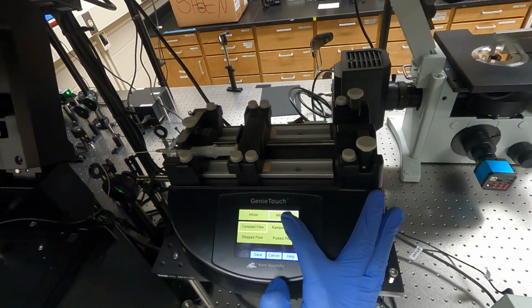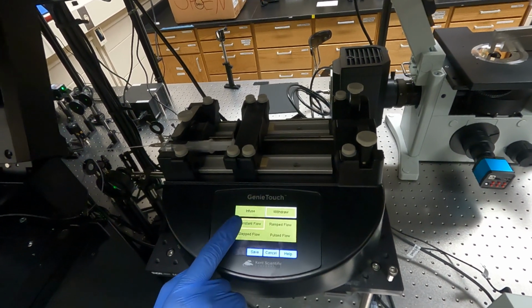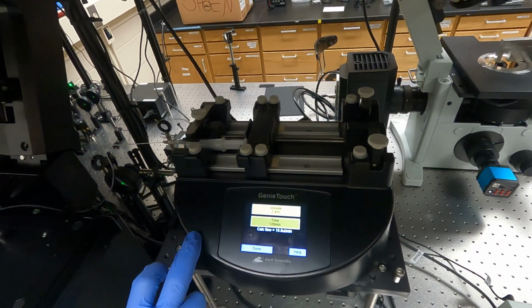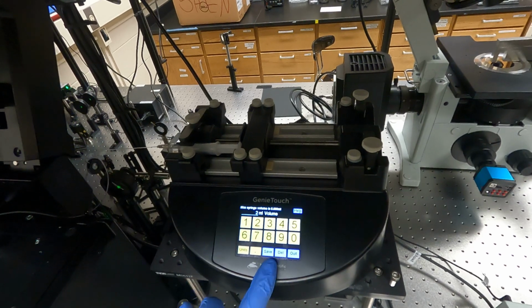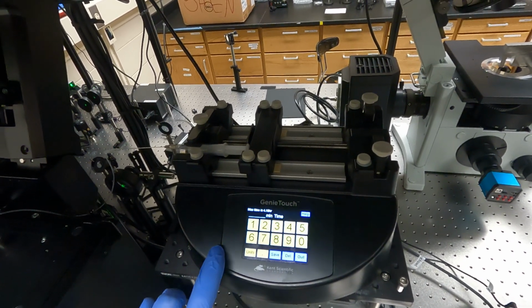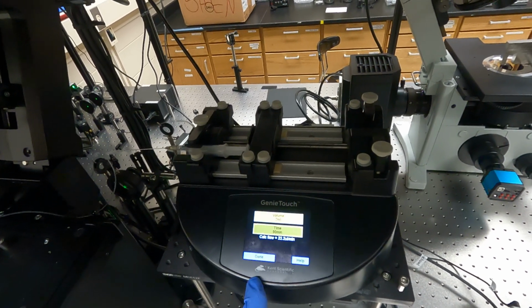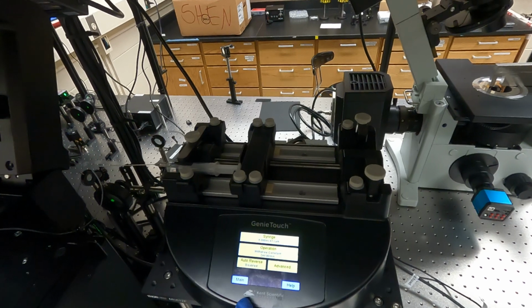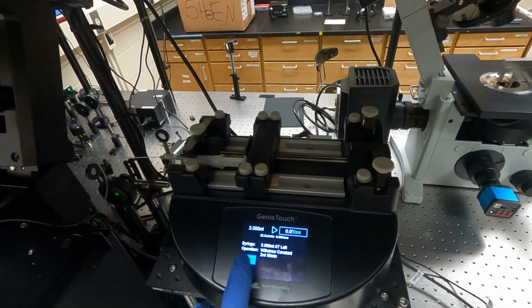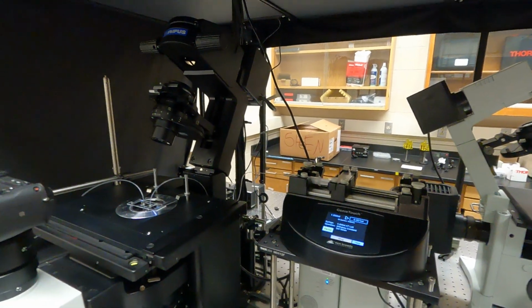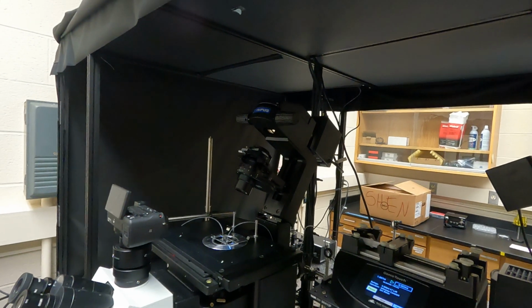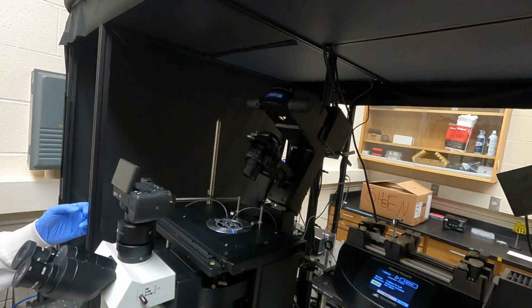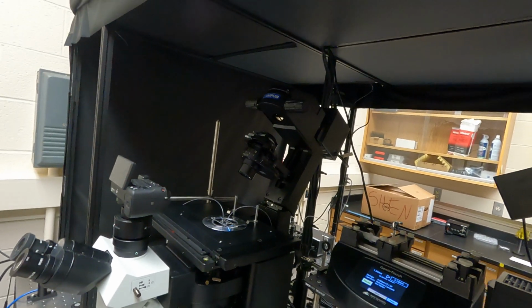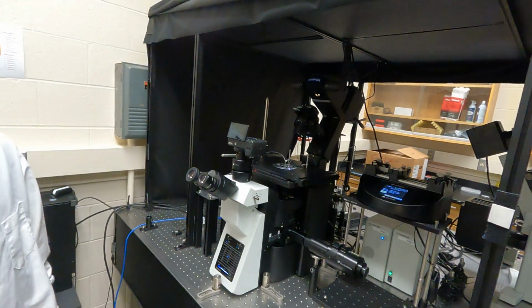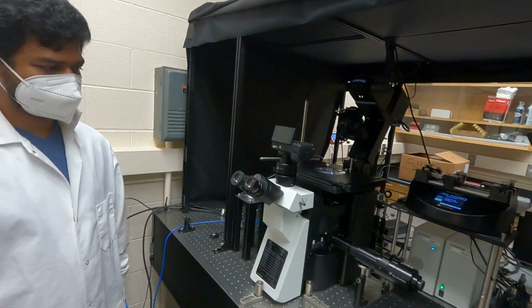The operation window tells you how fast you want the syringe to go. We use the constant flow mode. It will allow you to input the amount of solution you want to withdraw over a 90-minute period. From there, the flow rate is determined. Save the settings, and then click run. Then this syringe pump is in action. What we are doing is we want the syringe to suck the solution from the reservoir. We do not inject, but we actually suck the solution from the reservoir.